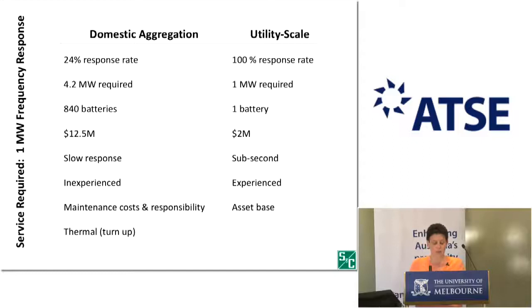Or you could deploy a utility scale battery. Utilities like batteries because it allows them to avoid reinforcement. There's a project in Queensland—well, it's not a project, it's business as usual now—where batteries have been used on single wire earth return circuits to provide additional support without needing to reinforce the lines. But there is an issue with utilities owning generation, because that's what batteries are classed as in Australia. They're classed as generation, and it's difficult for regulated entities to own and operate other regulated assets.